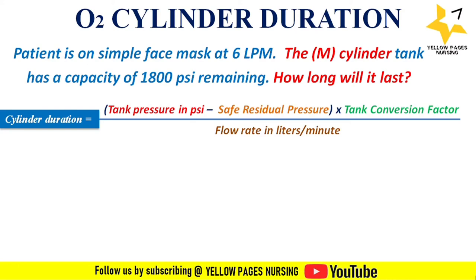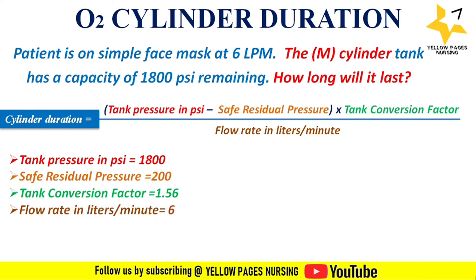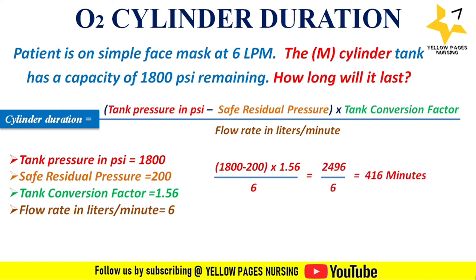Tank pressure in PSI is 1800, safe residual pressure is 200, tank conversion factor for the M-cylinder is 1.56, and flow rate in liters per minute is 6. Applying all values into the formula, we get the answer: 416 minutes. Converting this to hours, we get 6 hours and 56 minutes.